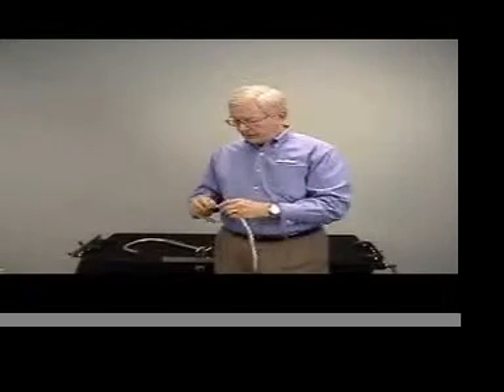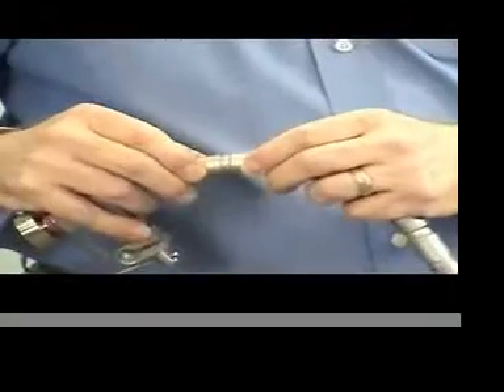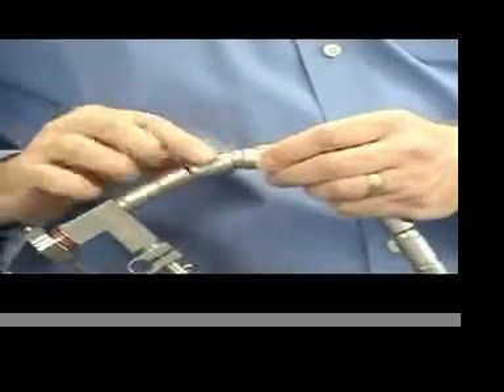Now, every FlexArm device is designed with a cable that is actually slightly longer than necessary. This is done for two key reasons. Over time, as you tighten the cable, it tends to stretch slightly. Or the open ends of the knuckles, when they're forced together time after time, tend to bell out slightly. This, in effect, shortens the overall length of the outer part and lengthens the cable. If there were no way to take up the excess slack in the cable, the arm would not be able to be tightened to its design maximum.